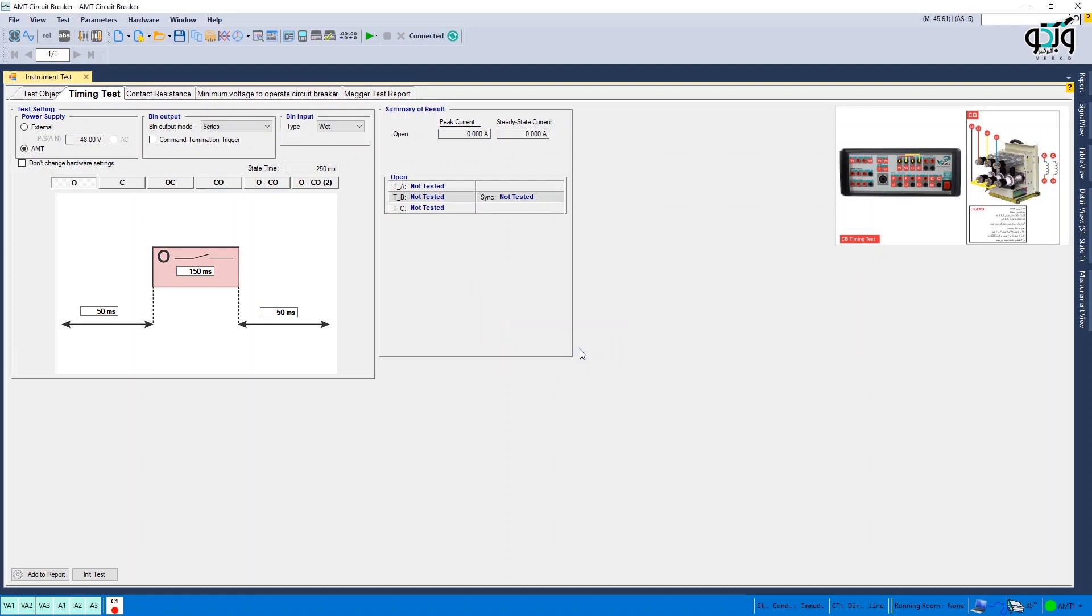Binary input is used to sense when the CB is closed or open. Since there is noise in substations, binary inputs are set at wet by default so noise is removed from the binary inputs.